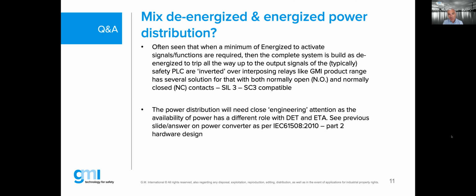Now, if the question was meant to be more about the power distribution itself, I mean the power distribution in your marshalling cabinet, in your junction boxes, etc., that also needs some close attention, because now the availability for energized to activate is different than for de-energized to trip. That is why it needs some engineering attention in the way of your I/O assignment, your wiring, your power distribution in your marshalling cabinet, all the way from a power supply over your fuses in your marshalling, etc. That needs very close attention.